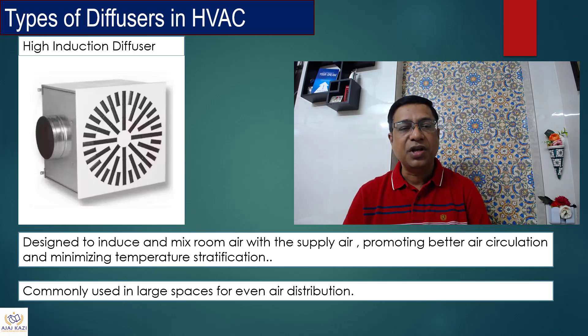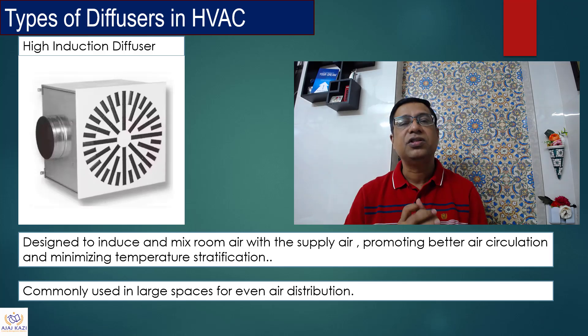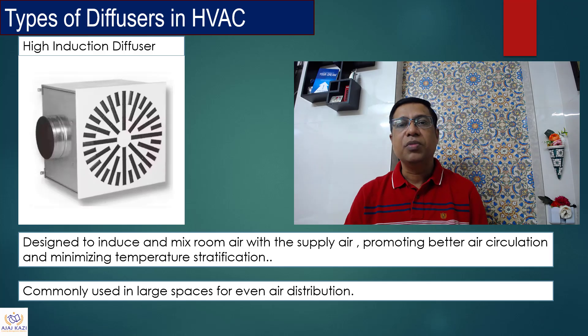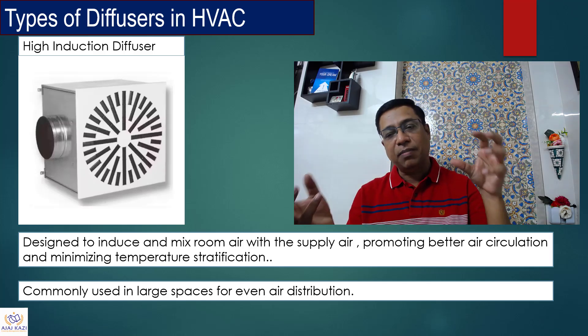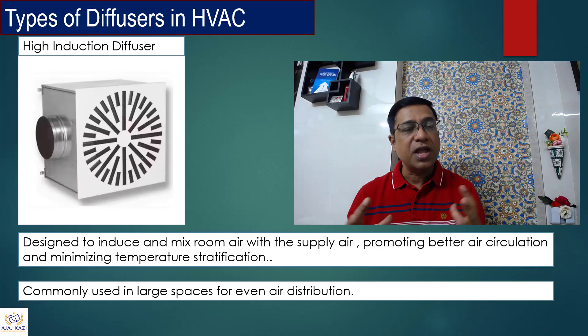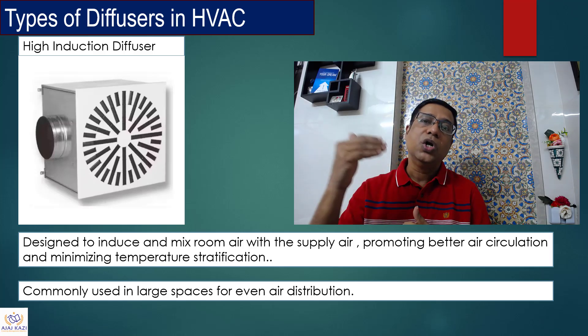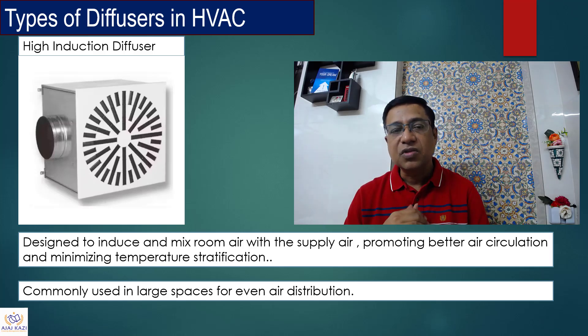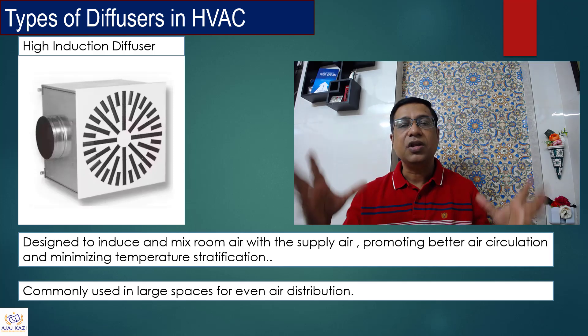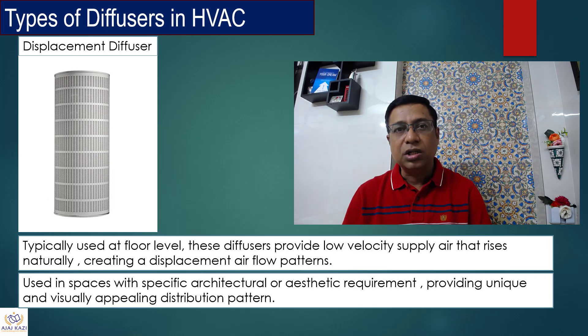High induction diffusers, as you can see from the image here, are designed to induce and mix room air with the supply air. Within the room, it takes the room air, combines it with the supply air, and actually promotes better air circulation and minimizes temperature stratification. This is why induction diffusers are commonly used in large rooms and large areas where you want to condition the air — you can use multiple of those and get a better cooling or conditioning effect.